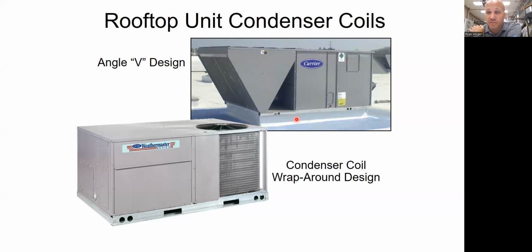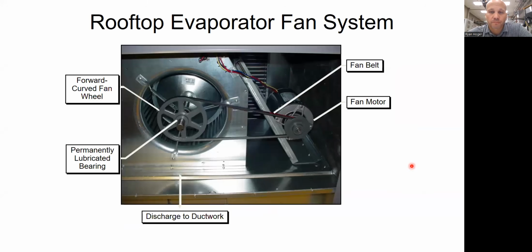So over time, what manufacturers have done to get more efficient, one of the ways to do that is to get a larger condenser coil surface area on here relative to the size of the compressor that you have. Well, you only have so much square footage on this guy. So going to one of these V-design type of condenser coils allows you to get more total surface square footage because you're cantilevering, you're hanging off the side of that curb with all of this extra over here. So that's one way that you might be able to get more efficiency. It doesn't mean it's always the most efficient unit when you see this V design. It just means that there's a pretty good chance it's on the higher efficiency side, at least at the year that it was built.